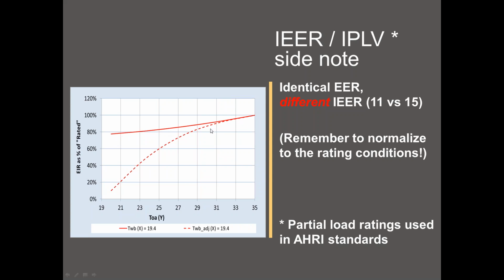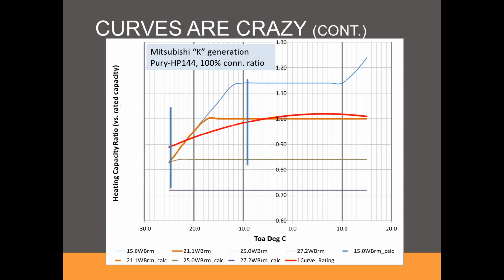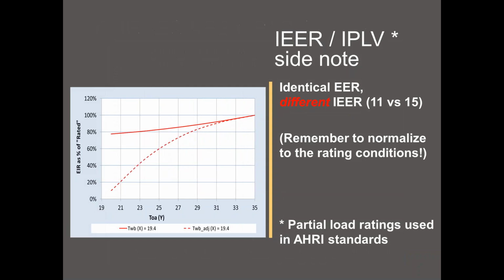If you haven't reflected this correctly in your curves, you will not get a good reflection of the actual performance in your energy model. So this applies to every DX coil, but the same principle applies to VRF coils, in particular because of their unique curve. In the case of a typical DX curve, a single curve representation works well, but you have to apply the curve coefficients well.